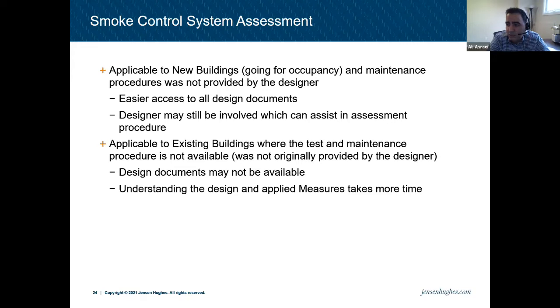So basically, when we deal with the smoke control system test and maintenance procedure, there are 2 scenarios that we are dealing with, and we have 2 different approaches. What is applicable to new buildings? Basically, going for occupancy, and the maintenance procedure is not provided by the designer. In a lot of cases, designers either don't know how to do it or are not aware of the requirement. So the building is going for occupancy and they don't have the test and maintenance procedure for the system. Technically, it's not a requirement, but as soon as the building is occupied, this is applicable to it, right? This becomes a fire code requirement.